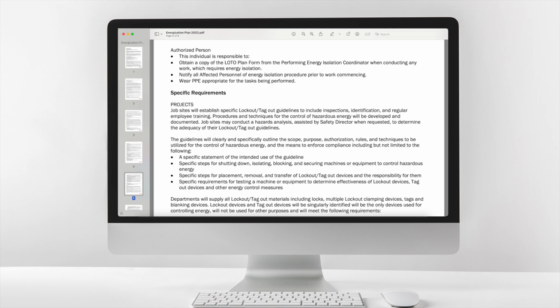statement of the intended use of the guideline, specific steps for shutting down, isolating, blocking, and securing machines or equipment to control hazardous energy, specific steps for placement, removal, and transfer of lockout, tagout devices and the responsibility for them, specific requirements for testing a machine or equipment to determine effectiveness of lockout devices, tagout devices and other energy control measures. Departments will supply all lockout, tagout materials including locks, multiple lockout clamping devices, tags and blanking devices. Lockout devices and tagout devices will be singularly identified, will be the only devices used for controlling energy, will not be used for other purposes and will meet the following requirements.